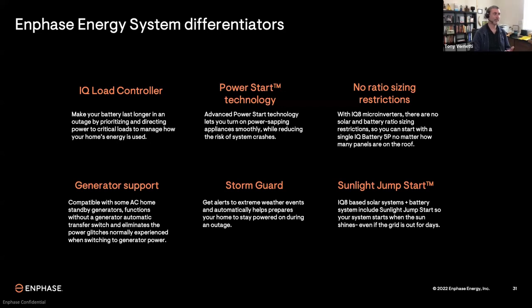And I just want to do a quick review of some of the additional benefits and differentiators of the Enphase system. We offer what are called IQ load controllers. Load controllers can be installed on any Enphase system, and they can be utilized to automatically disconnect certain large loads when the system goes into backup operation. Say there might be some loads that are potentially problematic in terms of how much power they demand, potentially have the potential to collapse the microgrid. You can set those up to automatically disconnect. You can also program this feature so that if the battery gets down to a certain state of charge, say 20% or 30%, whatever you enter, then those loads will be shed once it reaches that percentage.